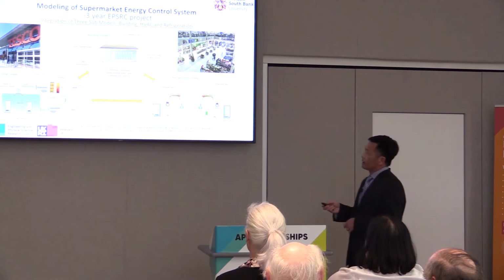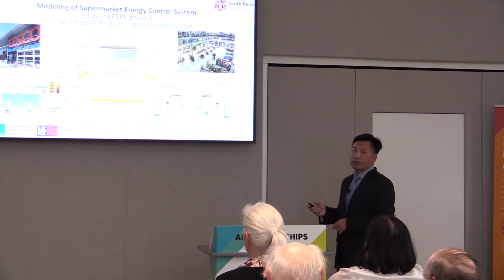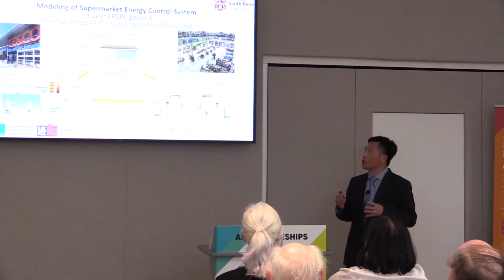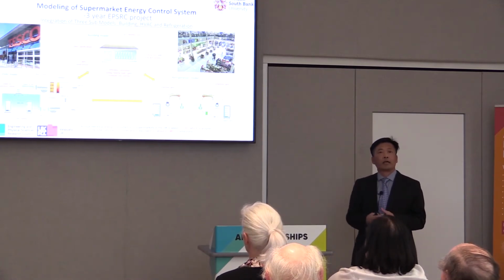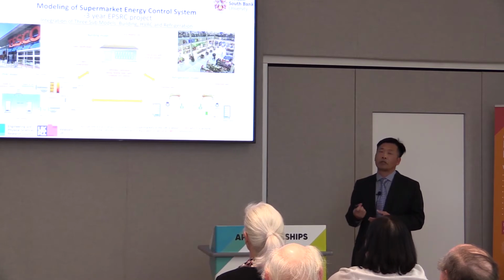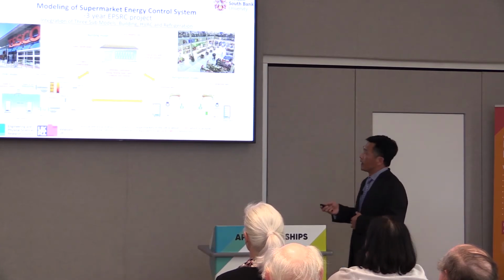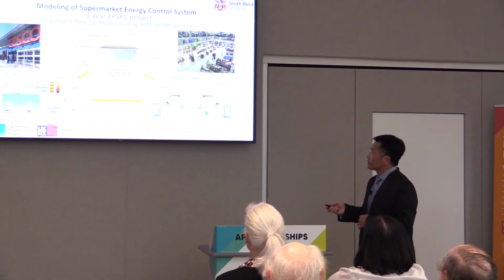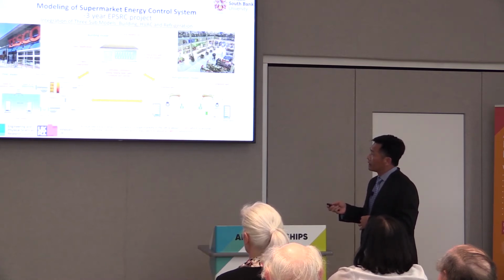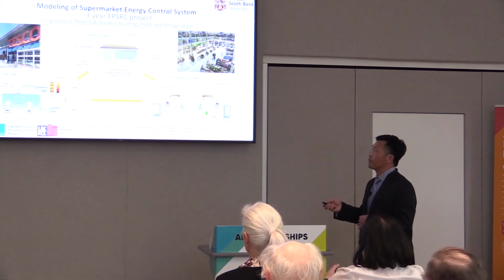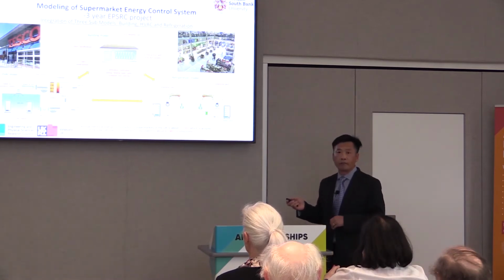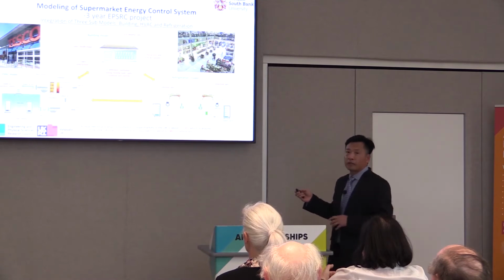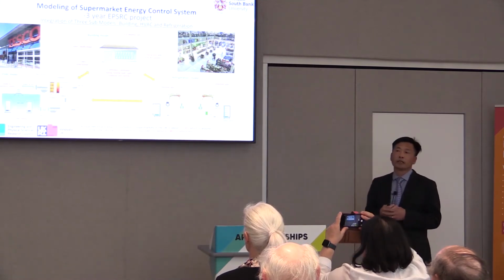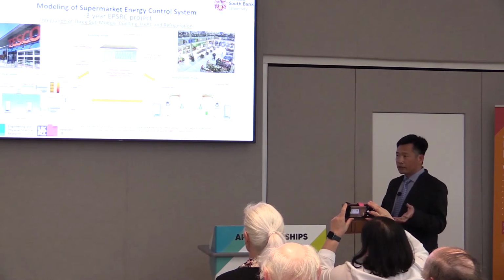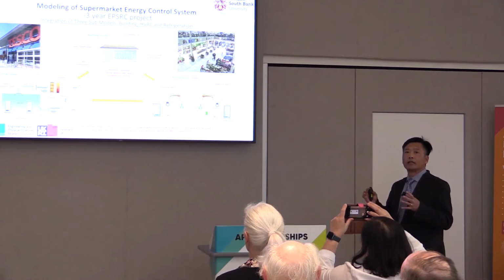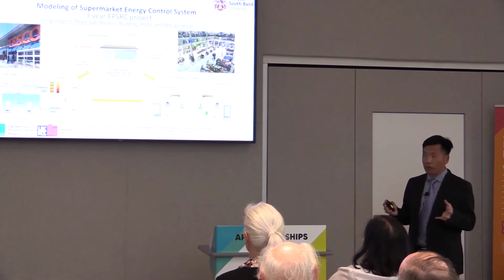And this is the HVAC system. The HVAC system is used to control the indoor air parameters in terms of temperature and humidity by means of this air handling unit. The air handling unit consists of supply and return air fans, a heating coil and a reheating coil. Because the refrigerated display cabinets in the supermarket are located in the sales area inside the building, they act as the heat sink of the supermarket.